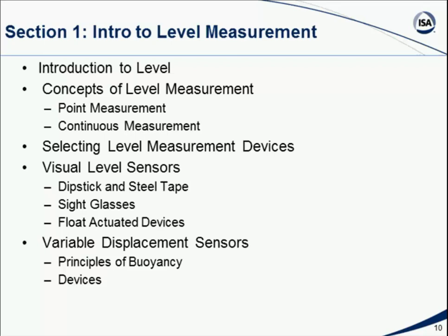We're going to talk about some of those, some of the type that provide a visual indication and that have been used manually and then, of course, can be adapted for automatic measurement purposes. We're going to talk about making measurement through indirect methodologies. For example, we're going to talk about the use of the principle of buoyancy as a way to make level measurements in situations where it would be very difficult to take any other kind of measurement.